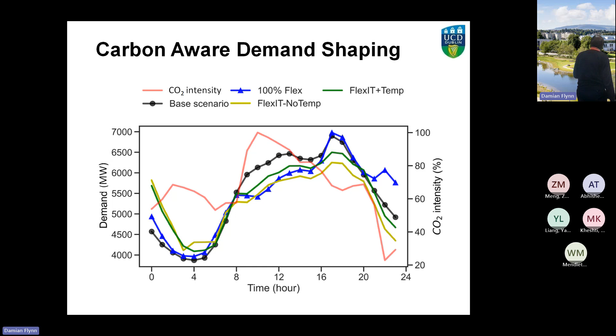The black dots show my initial curve. As I add flexibility controls, I'm able to reduce data server consumption at the high CO2 intensity times and increase it at other times, shifting the load away from high CO2 or high conventional generation periods and towards low CO2 or high renewables periods.